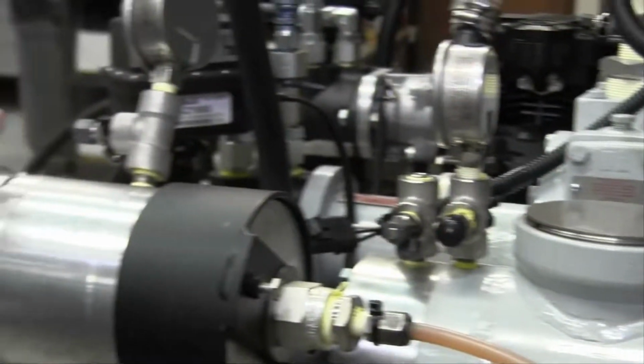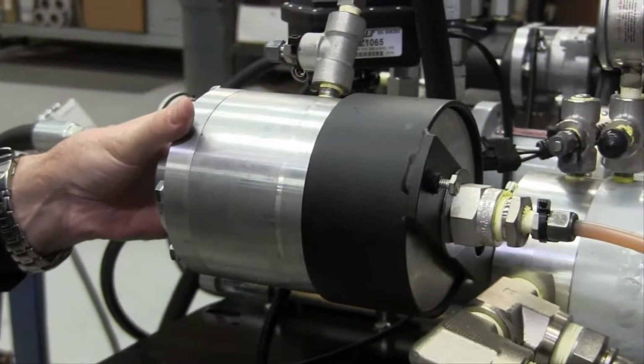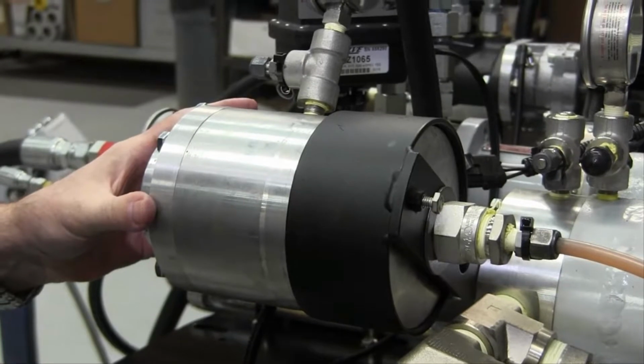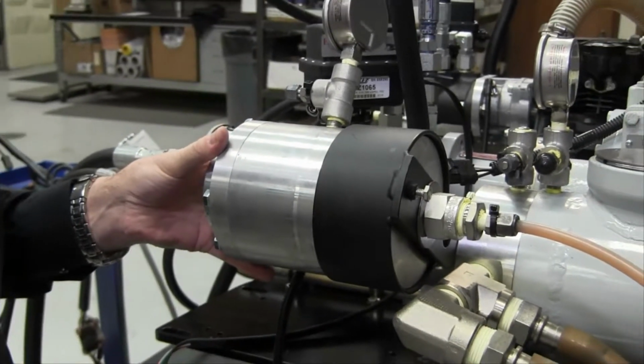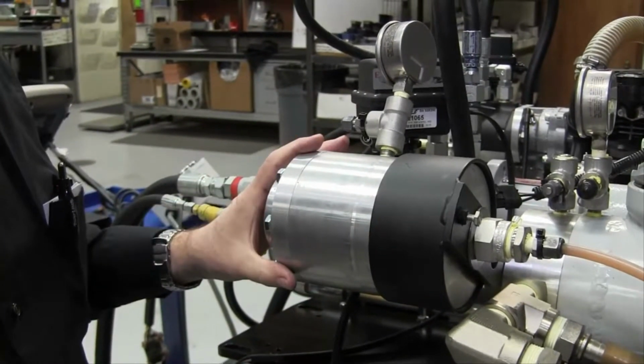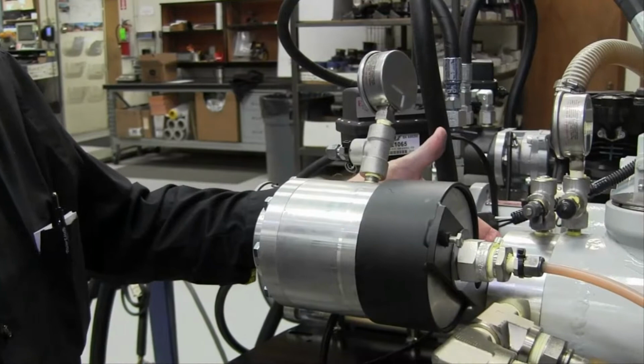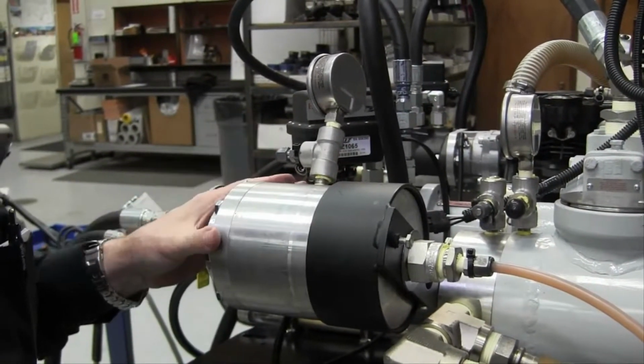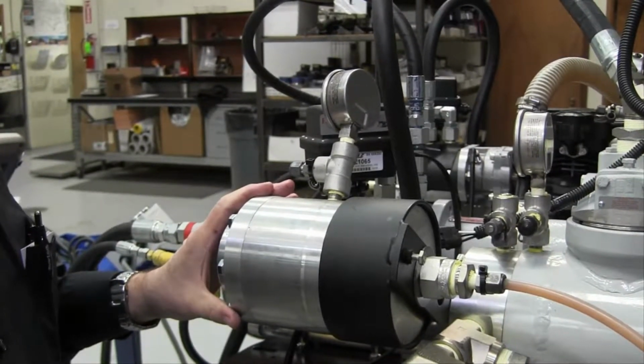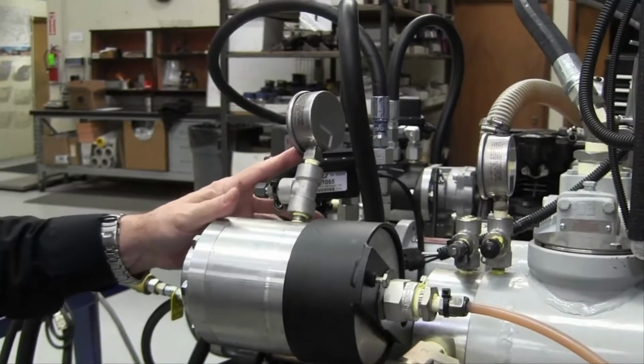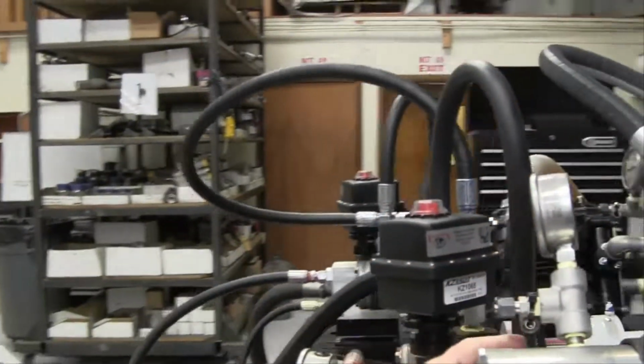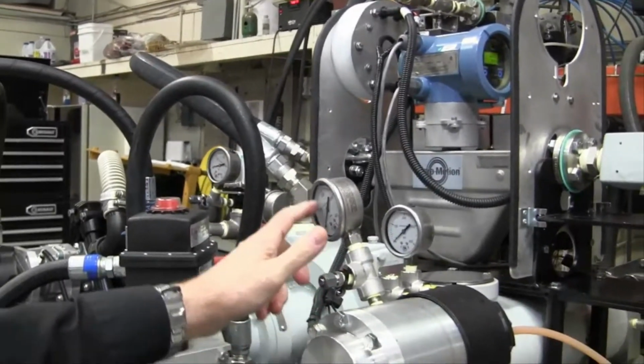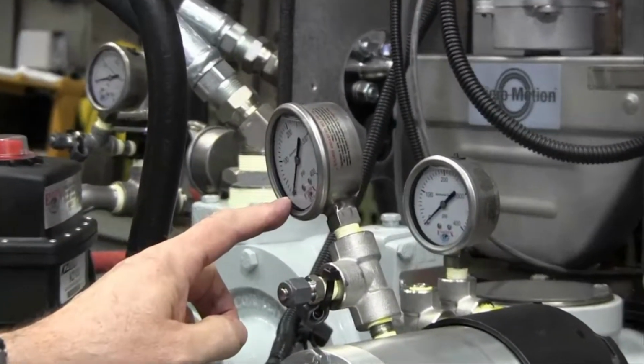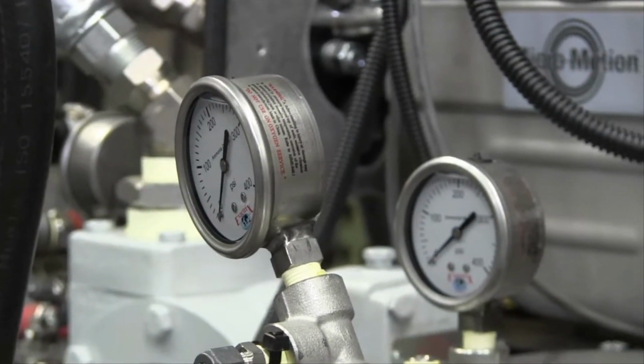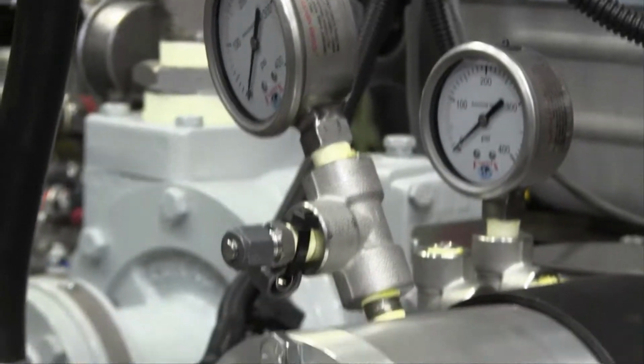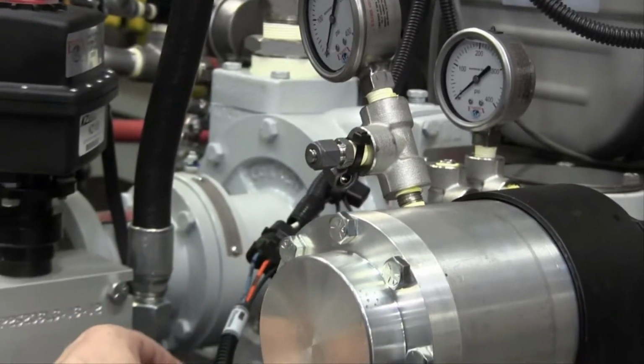And of course this housing here is another part of the phase shifter, and this is the phase shifter filter and reservoir, and it allows us to inject the flow of the vaporizer unit into here and actually chill for about 3 minutes after we shut down or before we start up. So we get a pre-chill with this system. It has its own pressure gauge on here, and so with this pre-chiller and filter, you can watch the pressure drop over time. It takes about 3 minutes for it to totally drain out with that small O21 orifice that's injecting the vaporizer flow into the system.